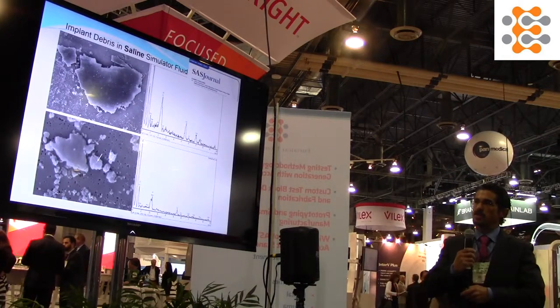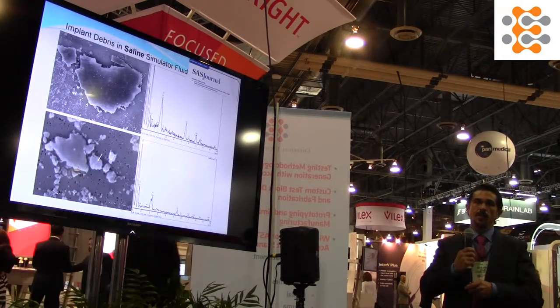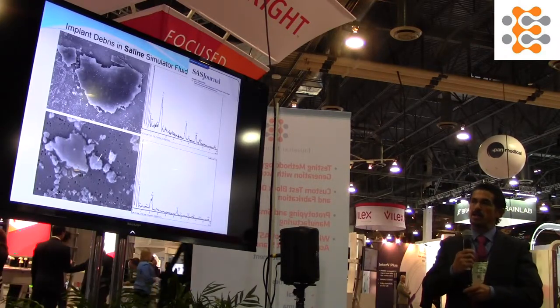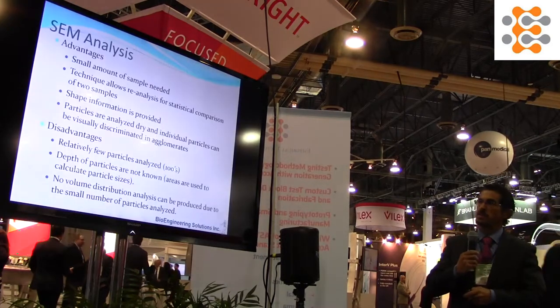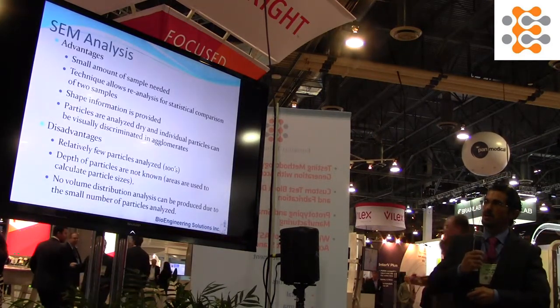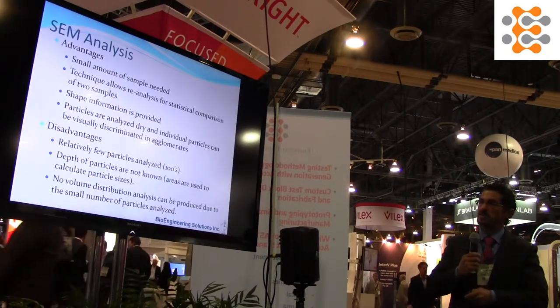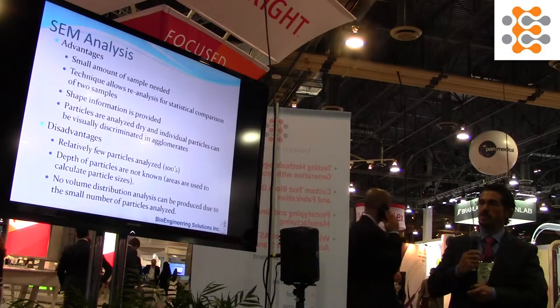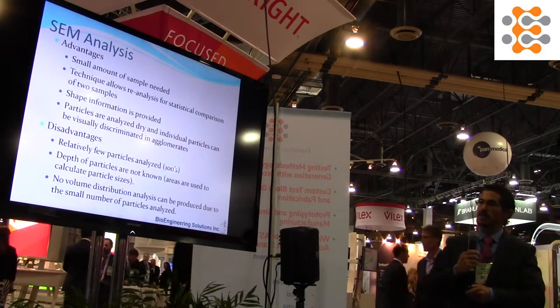Because a lot of times these days, the amount of wear is so low that contaminating silicone materials make up a large percentage of wear debris. The advantages of SEM are the small amount of sample needed and that shape information is provided. Its disadvantages are that relatively few particles are analyzed — hundreds, not the millions that are analyzed in low-angle light scattering.